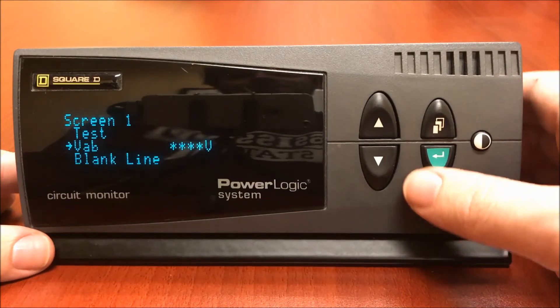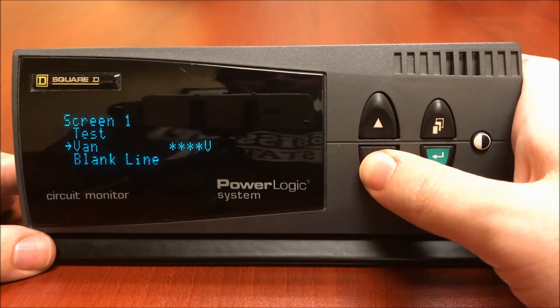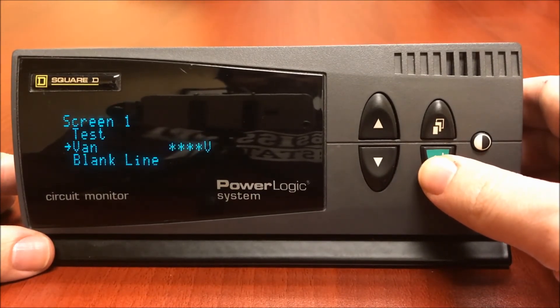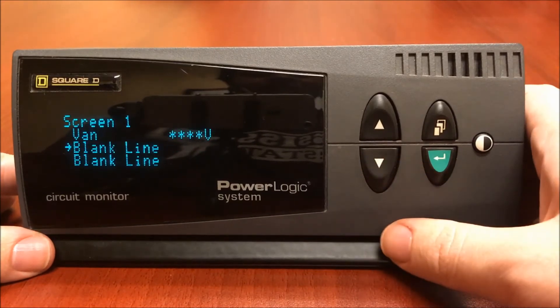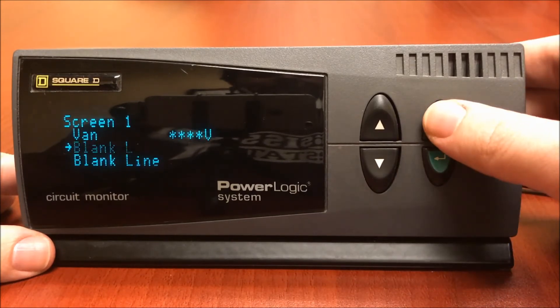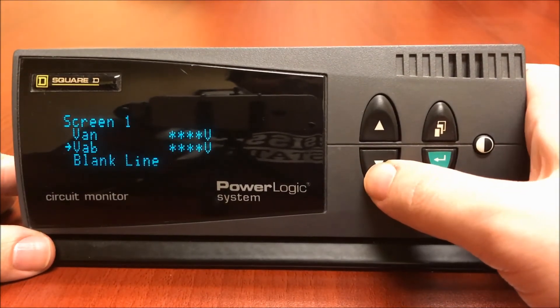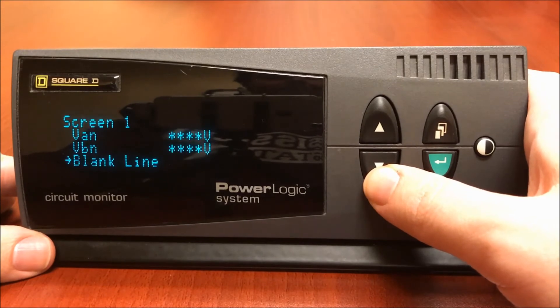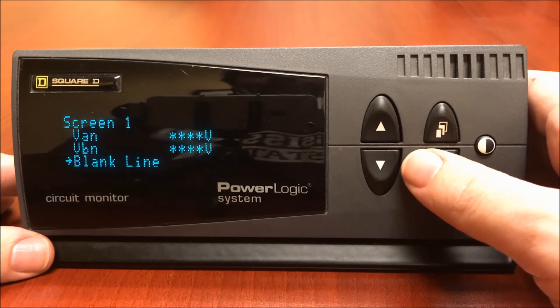Now I have different voltage measurements. I'm going to use voltage A to neutral. Once I have the measurement that I want, I'm going to hit the enter button to select. I now go to the next blank line — once again, hit enter. The blank line will start flashing. Now hit the measurement button. I'm going to choose voltage once again, hit enter. How about voltage B to neutral? And then once more we have a blank line again. You can only add up to three measurements under each screen.